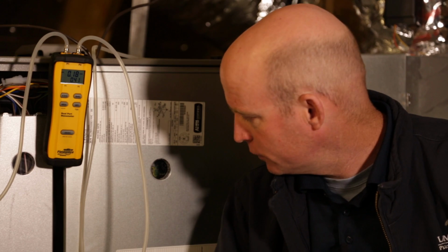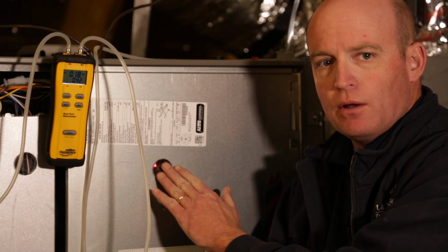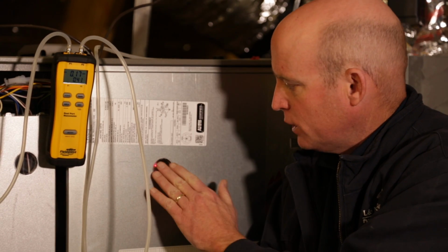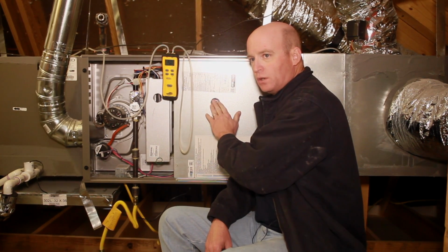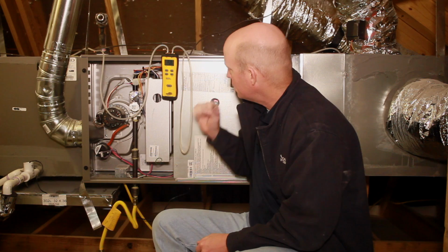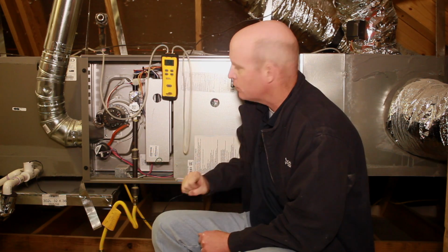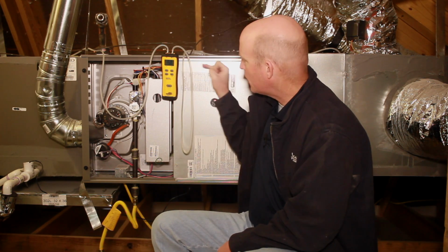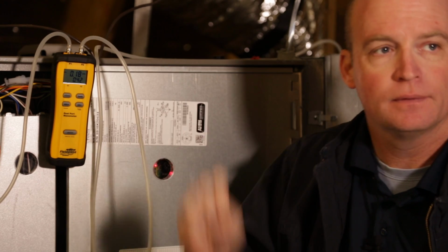This furnace also has the benefit of a digital readout. We can use that as a second confirmation, and we're all in the same ballpark. The main thing to be concerned with here, do not use the top number. Use the bottom number with this particular manometer. If you're using a different manometer, we may have to check to make sure you're looking at the right numbers.